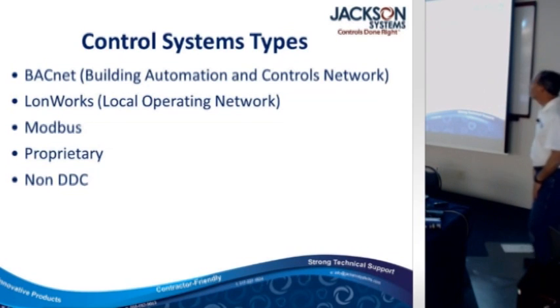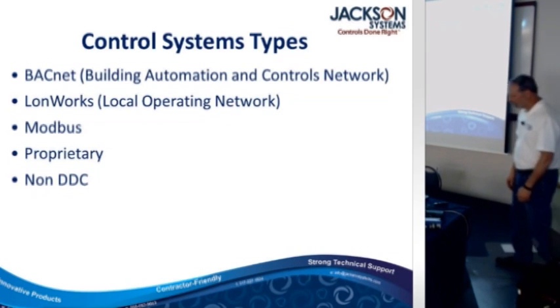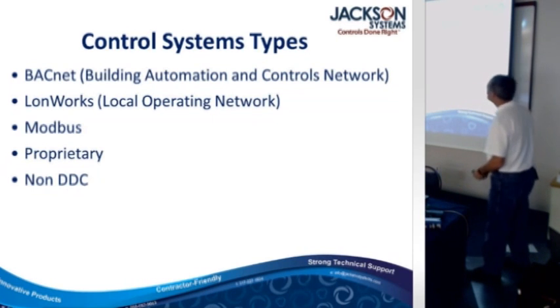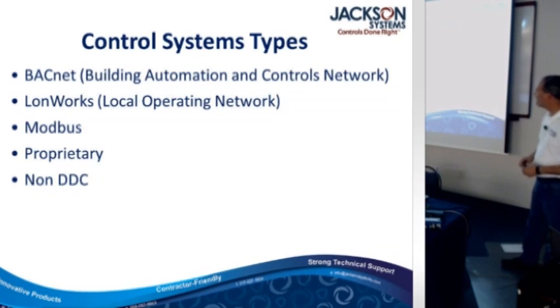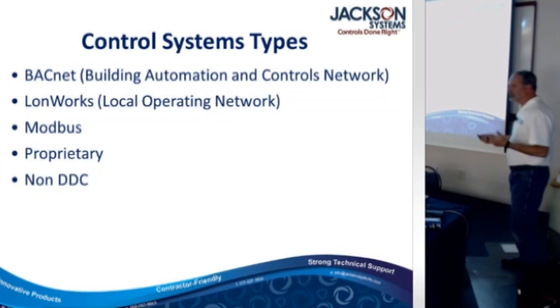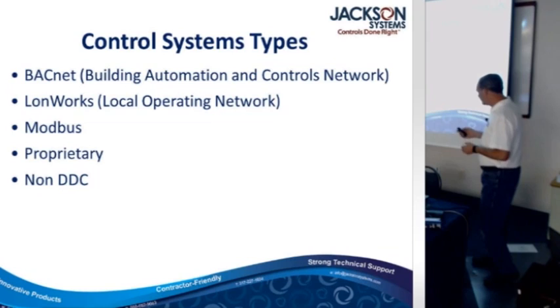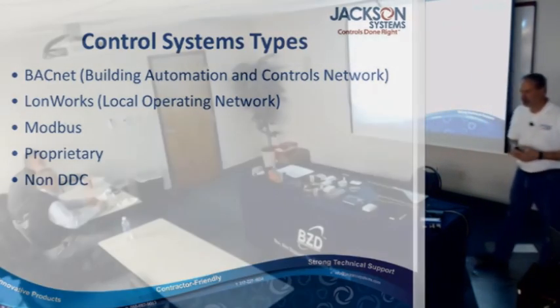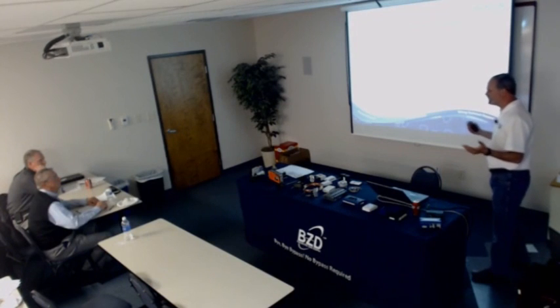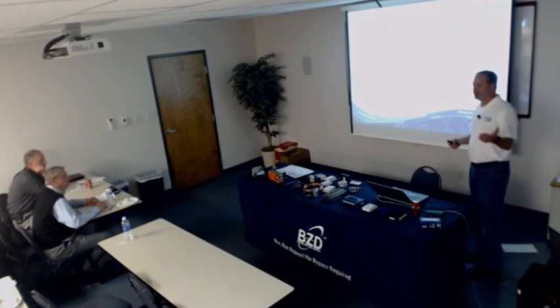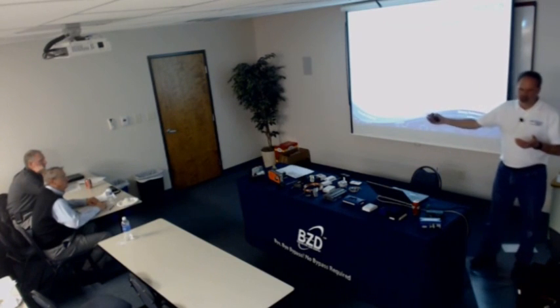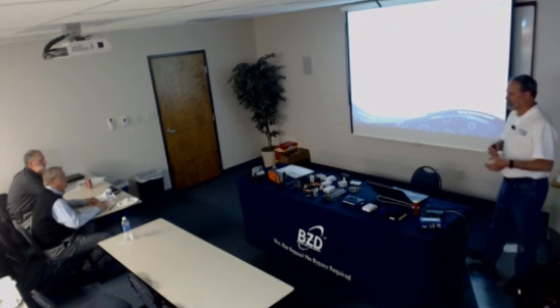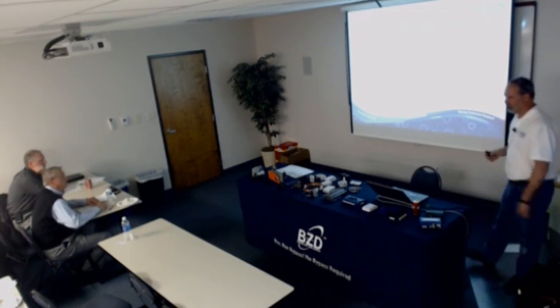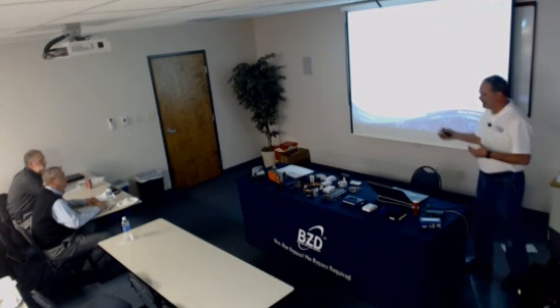So a little bit about some control system types. Probably the real leader in control system types today is BACnet. That's probably the one that's going to win. But there's its competitor, LonWorks. And I always explain BACnet and LonWorks to people like this. It's kind of like having a PC that runs Windows and a Mac over here. They both really do about the same thing, and actually they do them a lot alike. And you know, if you have a Mac machine, it'll run Microsoft Office even though it doesn't have Windows on it. So that's really what the difference between BACnet and Lon is.